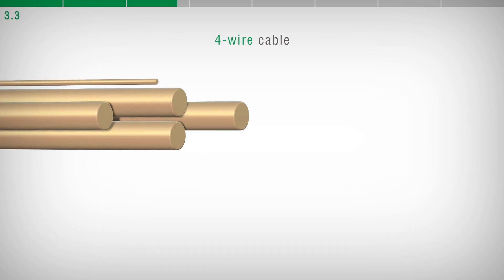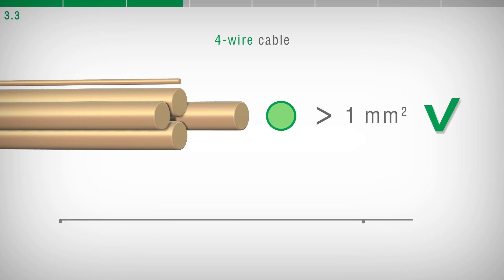When using four conductor connection cables, consider a minimum section of one square millimeter and preferably not exceed 300 meters in length.